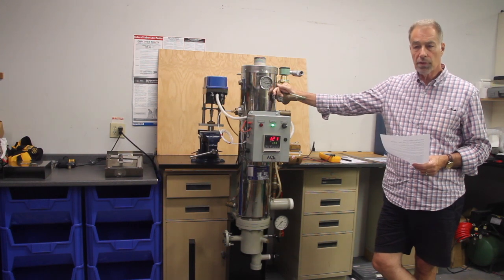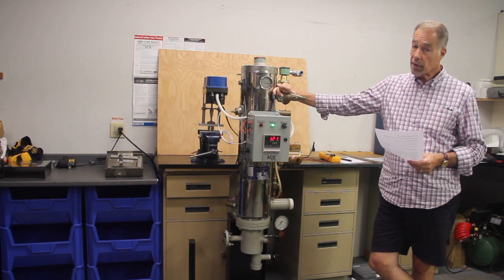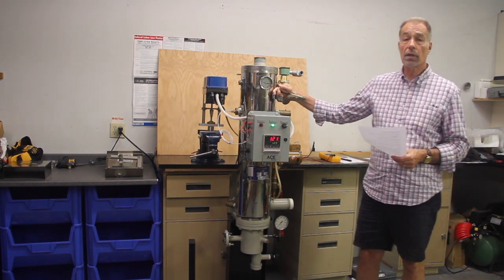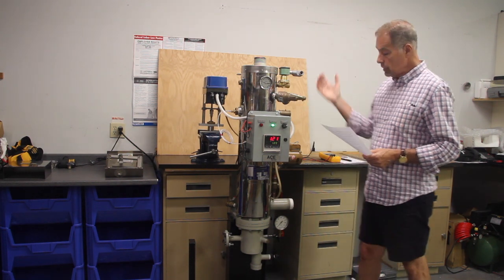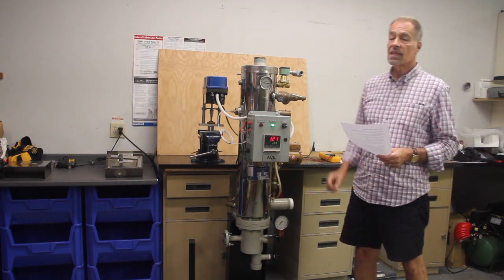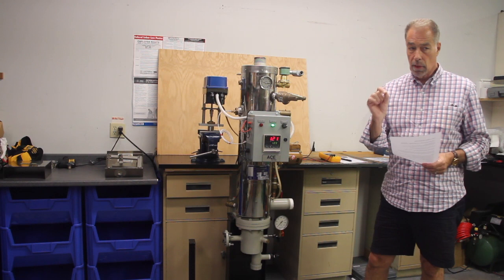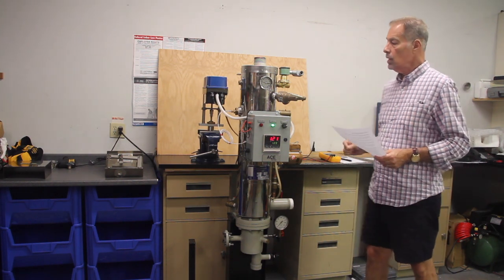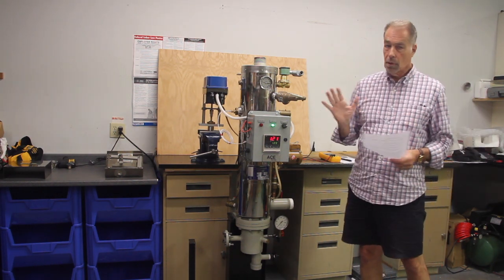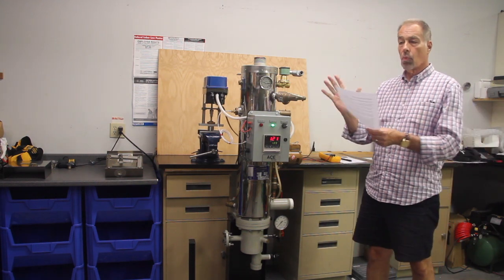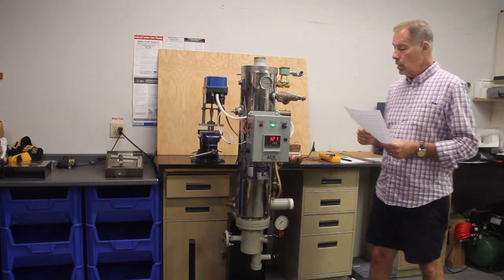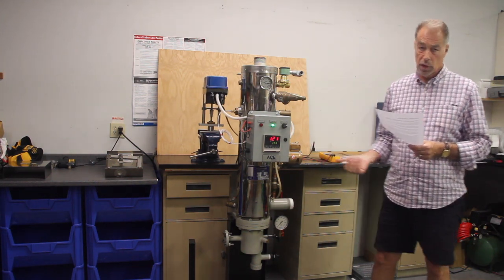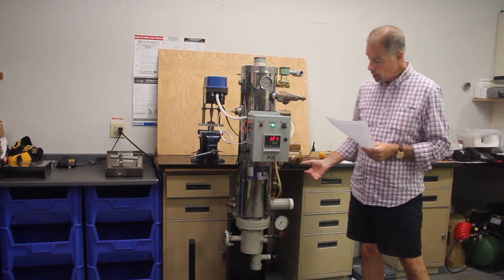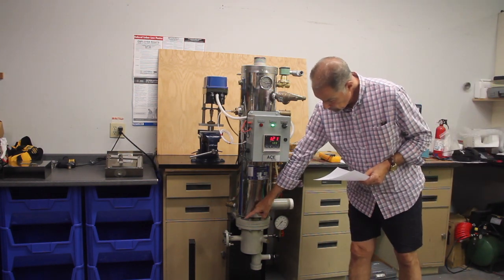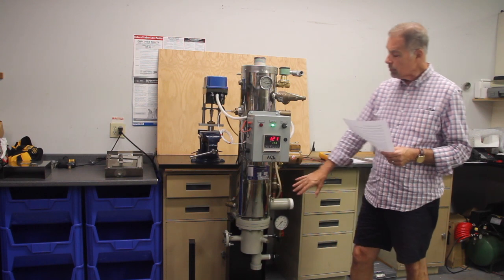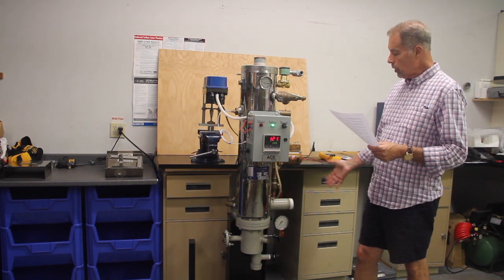It's not a storage device. It's not a direct fired device. It is an indirect, on-demand, in this case steam, semi-instantaneous. We're going to talk about what that means. But it needs either steam or boiler water from another source, and this is basically just a heat exchanger. Okay, we're putting primary boiler steam into the tube bundle, and we're making hot water.